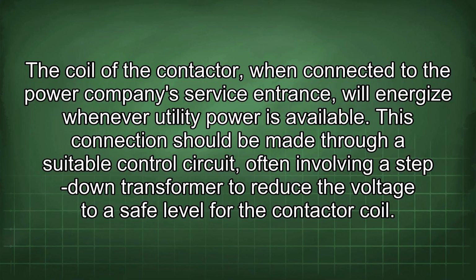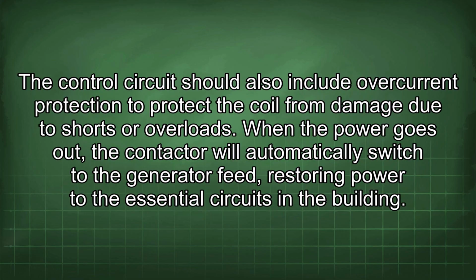This connection should be made through a suitable control circuit, often involving a step-down transformer to reduce the voltage to a safe level for the contactor coil. The control circuit should also include overcurrent protection to protect the coil from damage due to shorts or overloads.